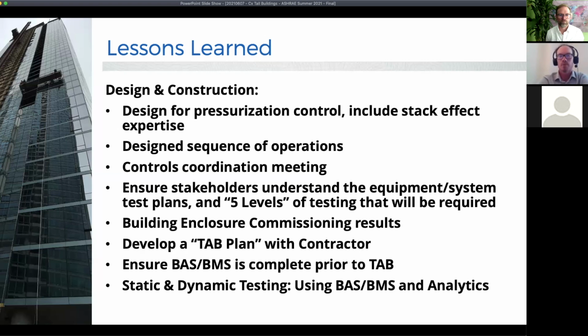So the next point, when I talk about ensuring that the stakeholders understand the 5 levels of testing, if we break that down fairly quickly, number one would be factory acceptance testing. There are some air handling units, and I would definitely be an advocate for having factory tested, pressure tested, just some simple checks. The commissioning provider could or could not be present for that.